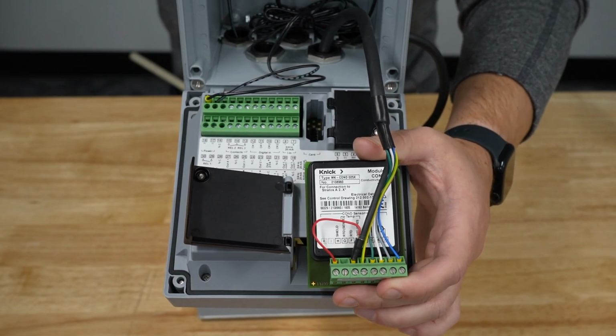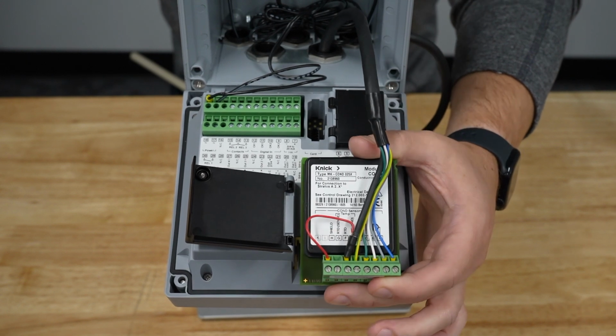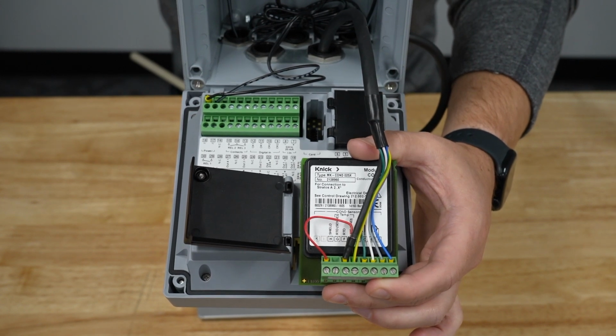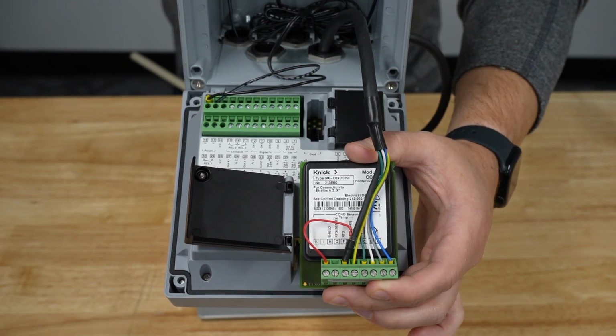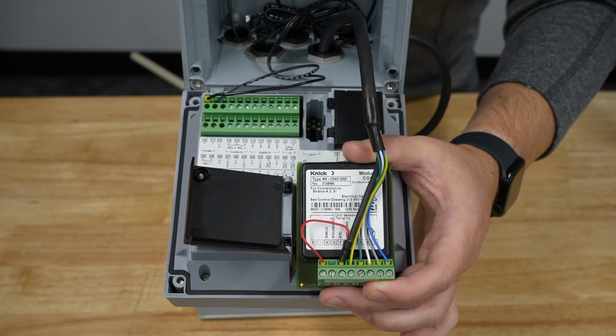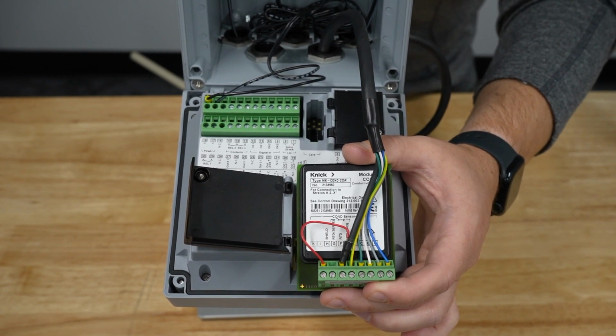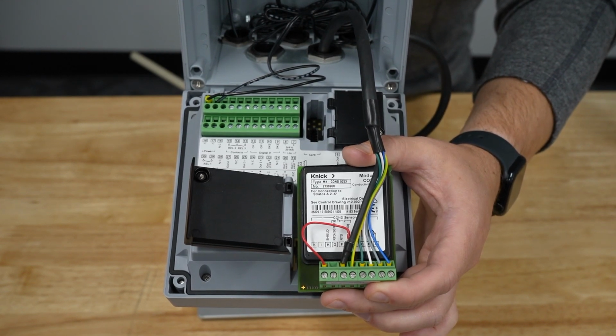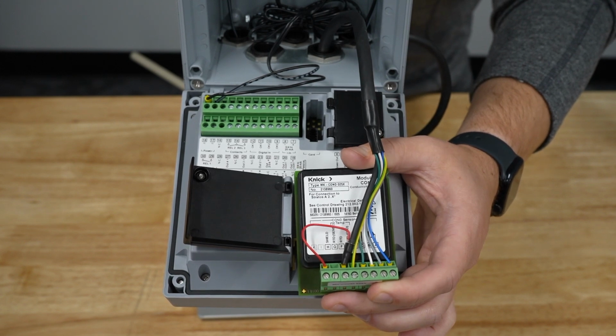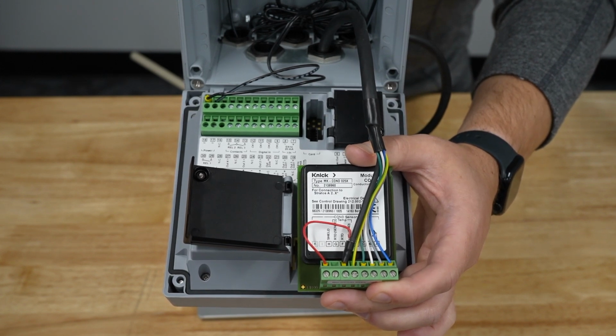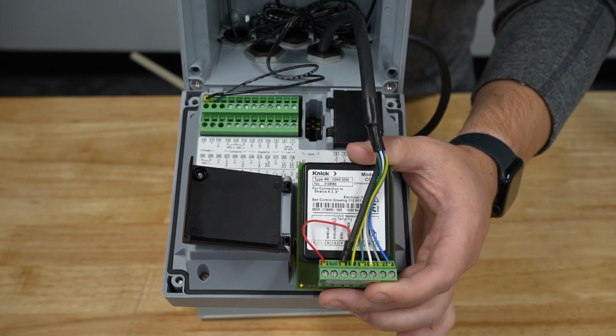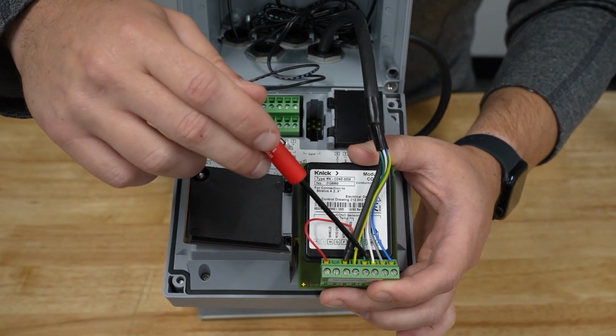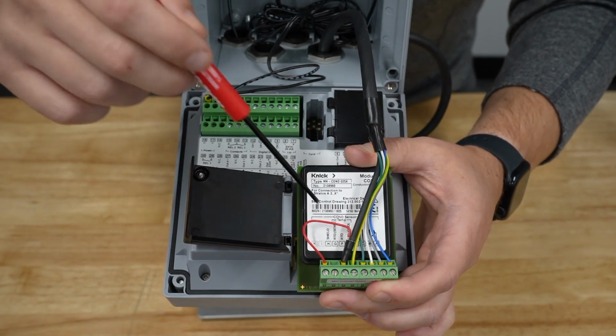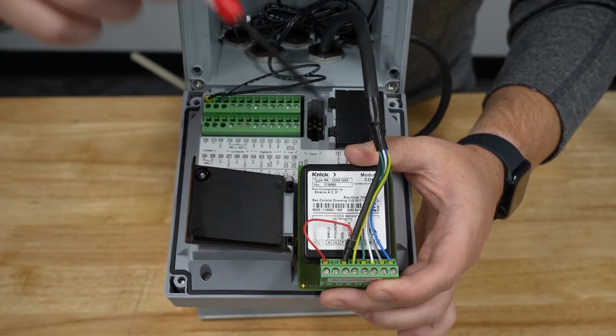When using the K25 with the Stratos Multi, an analog conductivity card will be needed. The wiring for this is as follows. The blue cable will go into the A slot. The gray cable will go into the B slot. The white cable goes into the C slot. The solid green cable goes into the D slot, while the yellow and green cable goes into the E slot.